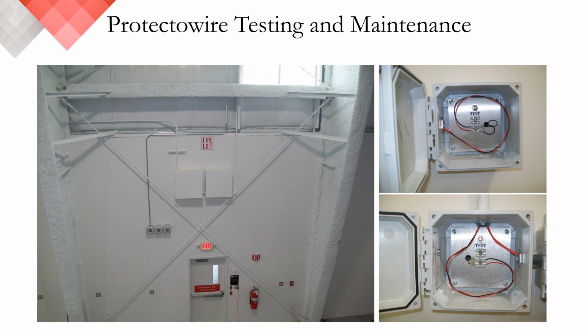Considering the testing requirements of line type heat detection versus spot type heat detection, you can quickly see the advantages of working with linear heat. In this slide, we're looking at an aircraft hangar with approximately 6,000 linear feet of linear heat broken down into 3 zones. Protection is provided up in the ceiling area of the facility, with the appropriate zone boxes installed at the beginning and end of each zone. We're then able to transition back out of the zone with the appropriate feed cable to locate the end-of-line junction box in a convenient location.